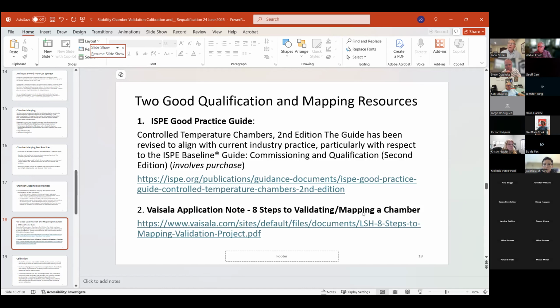Yeah, I think that's well said. A lot has to do with that mapping and whether or not you changed anything. And again, it's a great idea to come up with internal SOPs on how high you can stack things, have it in writing, with justification based on sound judgment, like the manufacturer's recommendation, safety recommendations, the amount of airflow, and whether it impacts your monitoring and mapping output.